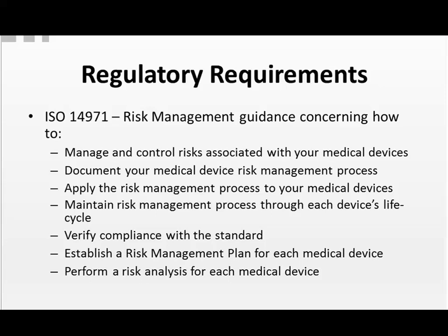for each device. Now, the ISO document provides a way in which a manufacturer can assess risk and make informed decisions. It's important to note that a medical device is not required to be entirely risk-free, nor does the document specify a specific risk acceptance level. The guidance document really leaves that up to you.